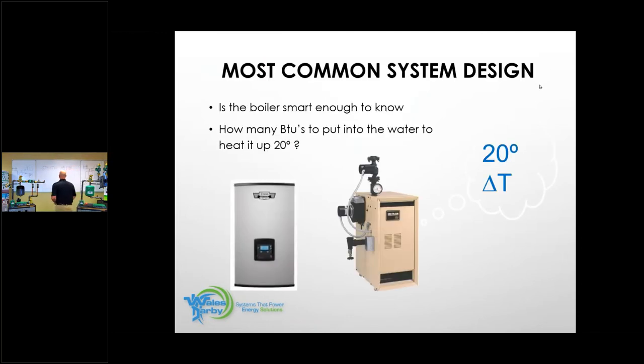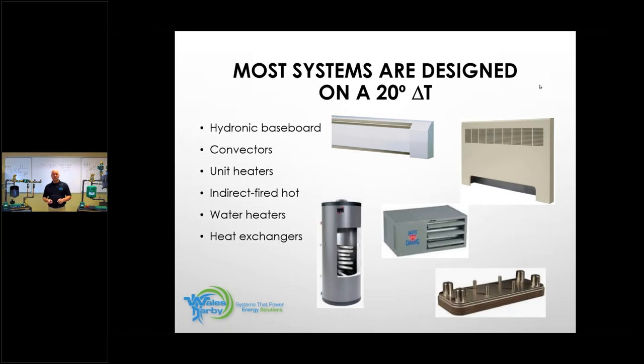So where does this 20 come from? 20 degree delta T. The majority of the boiler manufacturers out there all look for a 20 degree delta T, and that's where they're comfortable operating. When you get into the condensing marketplace, as the boilers get larger, some manufacturers may offer you a 30 degree delta T. Okay, and we'll go through a whole bunch of different delta Ts and get you familiar with how to do the math.